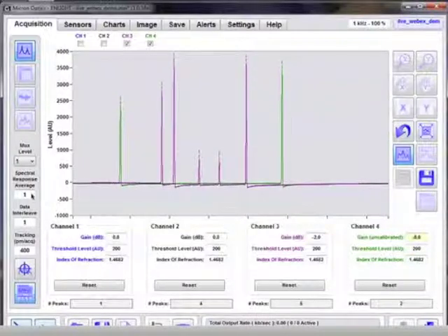So if acquiring from a 2 Hertz interrogator, you apply 2 averages, effectively the time response of the entire system will be brought down to 1 Hertz, and you'll get a square root of 2 reduction in the noise of the spectrum itself before peak detection. Okay?